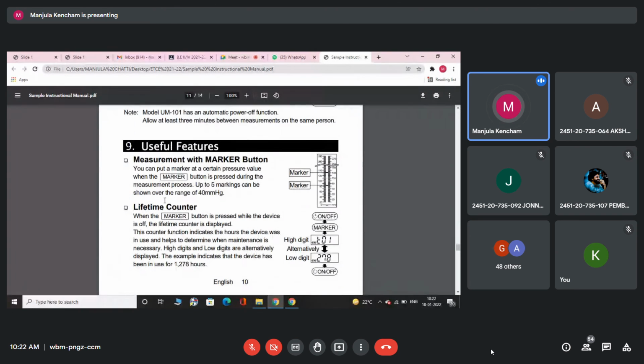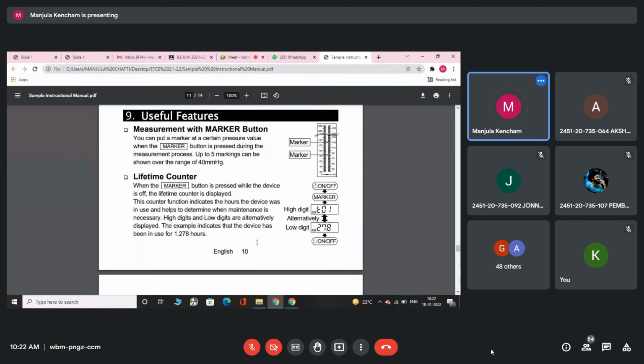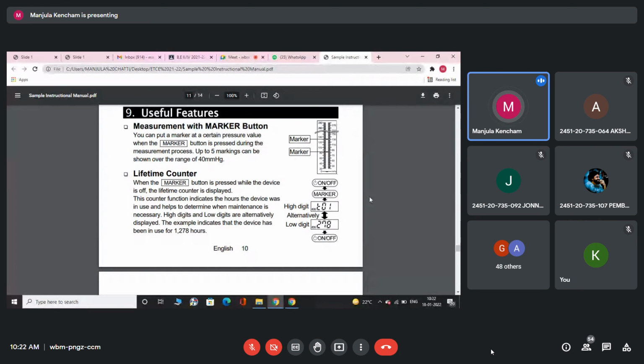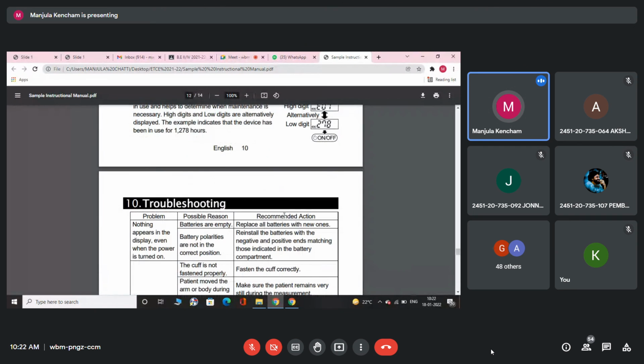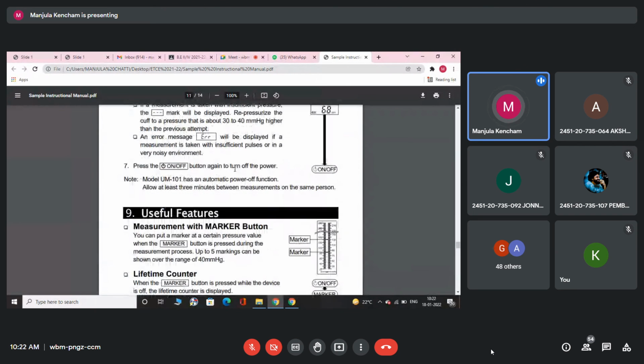Okay, useful features. Measurement with marker button. Lifetime counter. The hours the device was in use. Say if I have used it for too long, it needs maintenance. That is when I should take it to the maintenance service department, and people would set it properly and give it back to me. Fine, that is up to its usage.